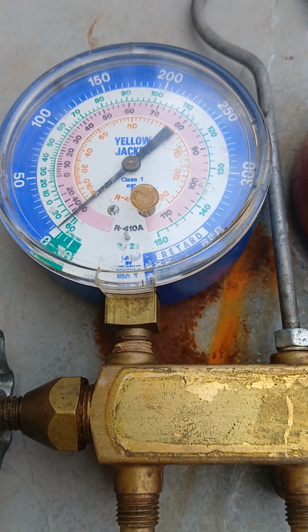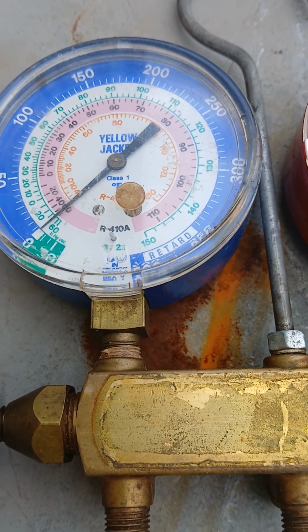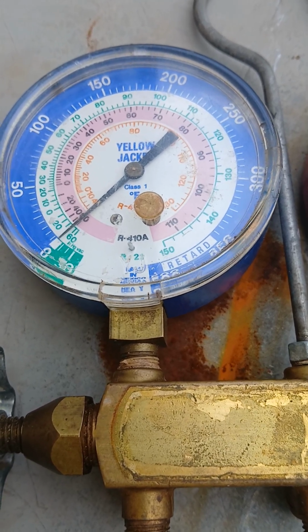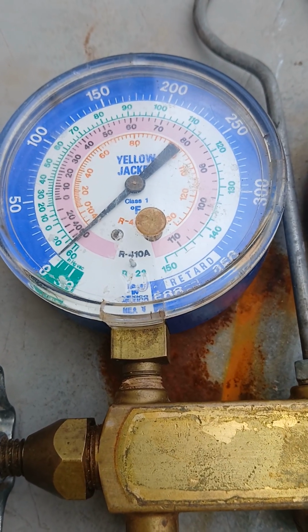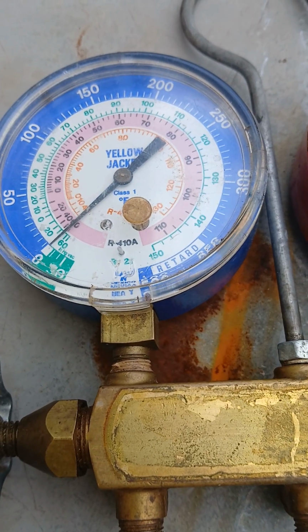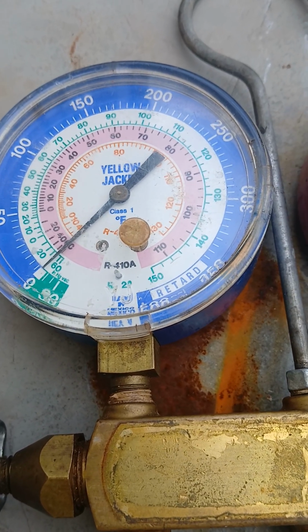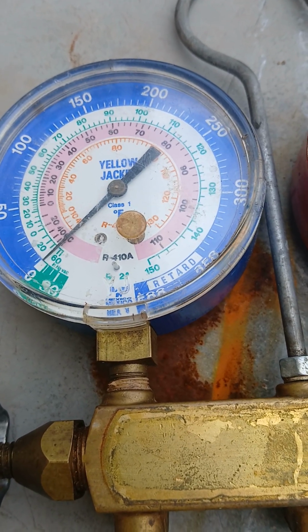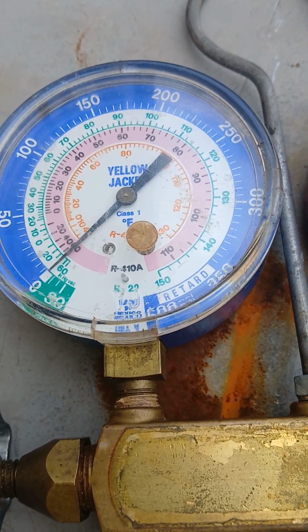So now what does this indicate, or what is it a telltale sign of? Say hypothetically one has a split unit with copper pipes, and comes out and notes that the larger line, the suction line, the low pressure line, has frost or ice on it. At this point one may wonder, well, what's going on here? If the line outside has frost or ice, the A coil, either in the house, in the closet, or in the attic, could already have ice on it.